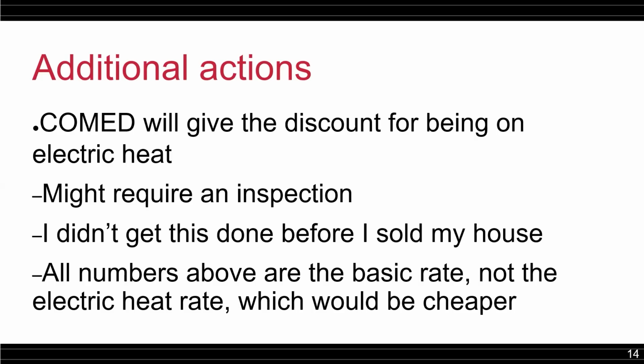On mine, the electrical box disconnect, the breaker inside, all that stayed the same. None of that changed. I just took the heat pump up, even though it was a 4.5 ton versus a 3.5 ton. It all got hooked up to the same circuit, all rated for that circuit size, and everything was fine. On the indoor side, I had to run a big heavy wire over to feed that indoor unit for its backup heat. That's a different animal.